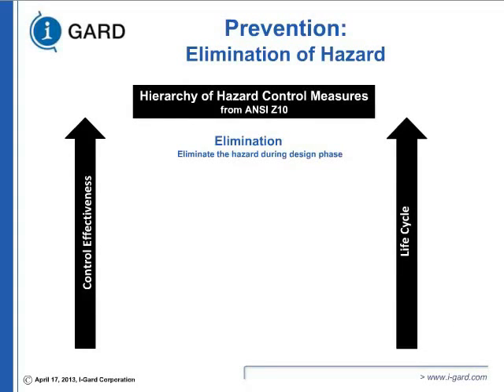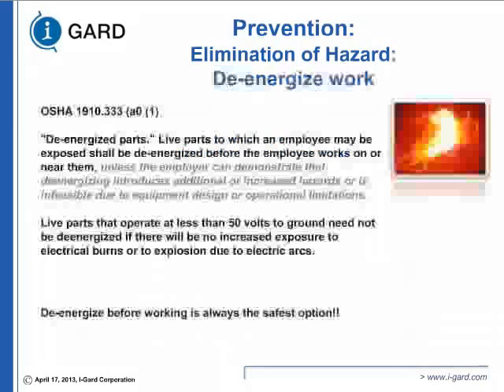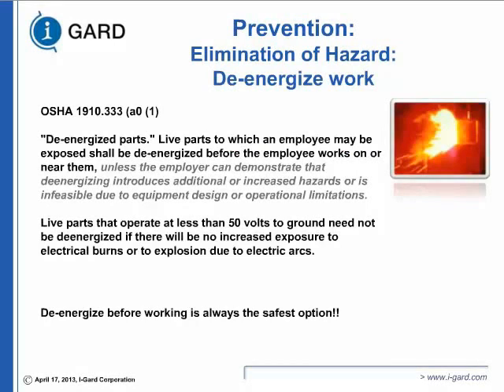Let's address the first item, elimination, and how you can eliminate the hazard. In the United States, there is an agency called OSHA, and 1910.333 tells you that live parts to which an employee might be exposed shall be de-energized. If you are reading this slide, please keep special emphasis on the next phrase: before the employee works on or near them. And highlight the next item: unless the employer can demonstrate increased hazard or infeasibility. The responsibility to demonstrate is by the employer.